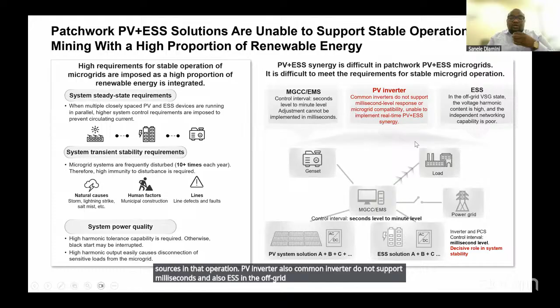So looking at the patchwork, the ESS vendor will be different, PCS will be different, transformer, inverter, and so on and so forth. So this will actually give you a lot of problems because if you've got a vendor A and a vendor B, and as a mine, you say the problem is sitting on vendor E as an inverter. So that means if vendor E comes there and tells you that no, the problem is actually sitting on vendor C, a transformer, and the guy from transformer vendor C comes and says, no, the problem is sitting on vendor A, a battery. So now you have lost time, of which mines are very sensitive when it comes to time.